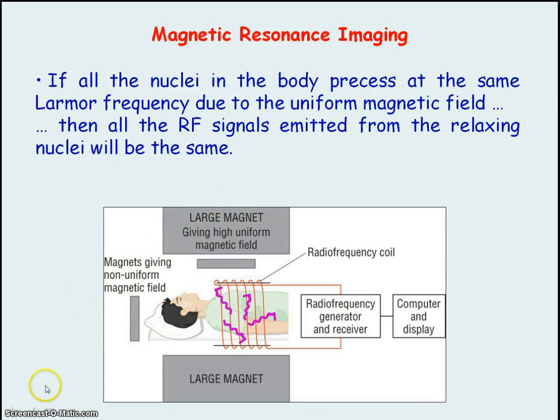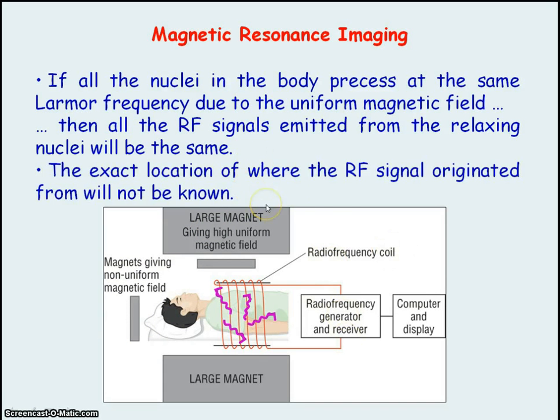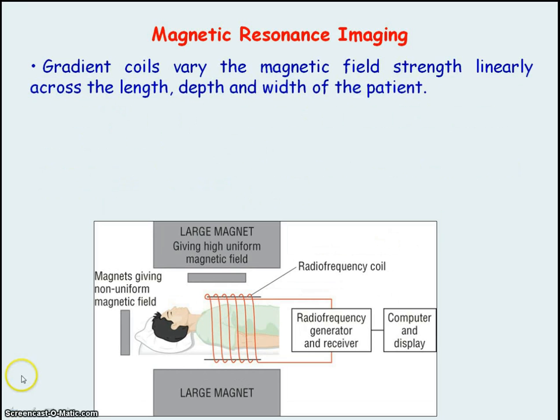If we didn't have the gradient coils, all the nuclei in the body would precess at the same Larmor frequency due to the uniform magnetic field produced by the large superconducting magnet. As a result, all relaxing nuclei would emit the same radio frequency signal, and the receiver coil would pick up these signals, but the exact location where each signal came from would not be known.